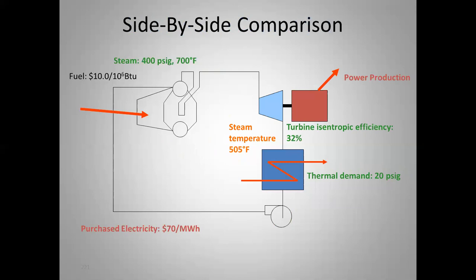Through the steam turbine: we get power output, and the steam temperature drops to 505°F because energy is extracted and converted to electricity. With the same thermal demand of 35.5 million BTUs per hour but less energy in the steam, we need to generate a little more steam to supply the same heat to the process.